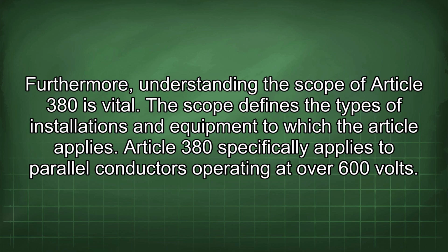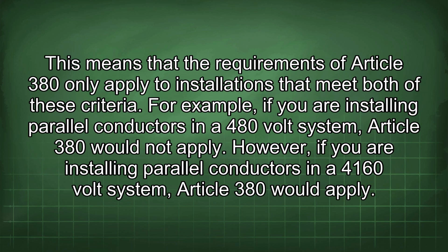Article 380 specifically applies to parallel conductors operating at over 600 volts. This means that the requirements of Article 380 only apply to installations that meet both of these criteria. For example, if you are installing parallel conductors in a 480 volt system, Article 380 would not apply. However, if you are installing parallel conductors in a 4160 volt system, Article 380 would apply.